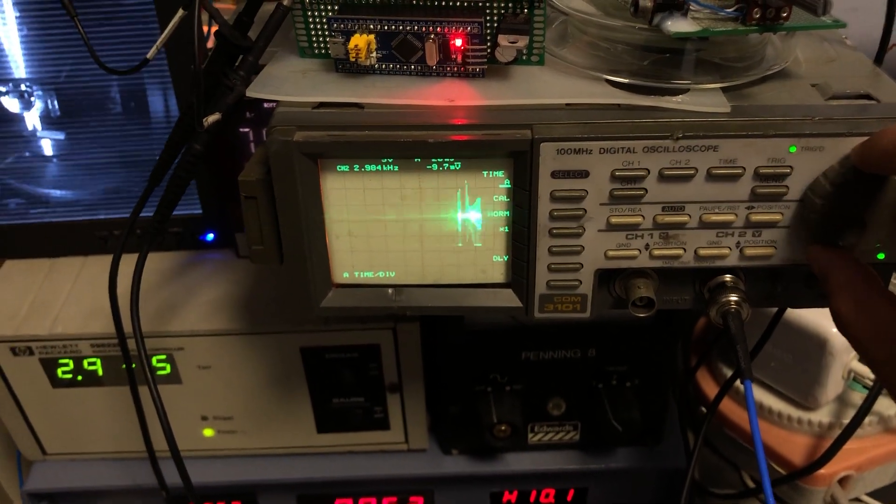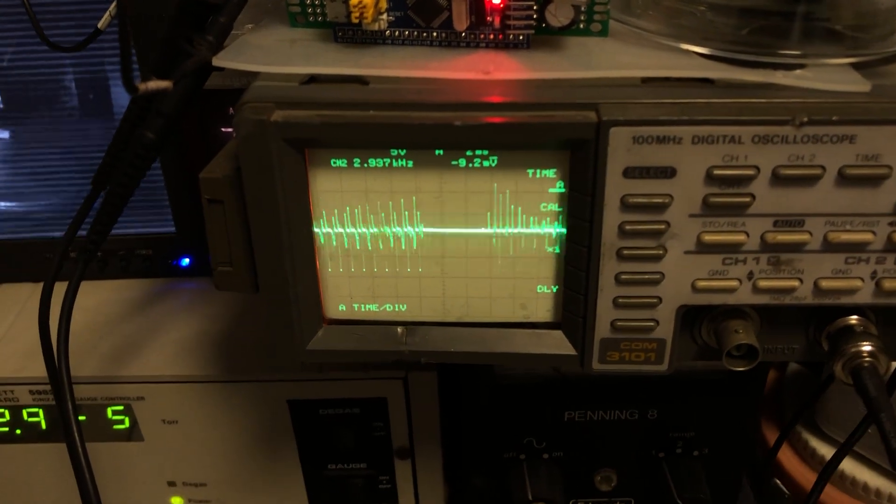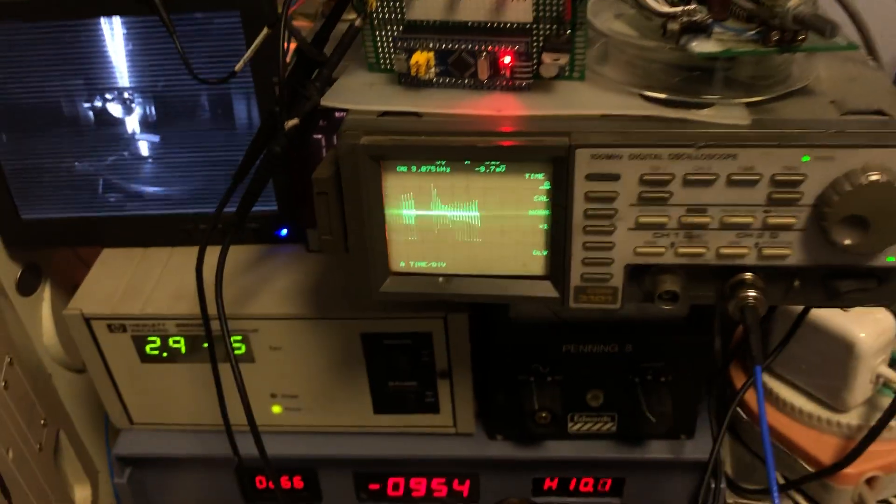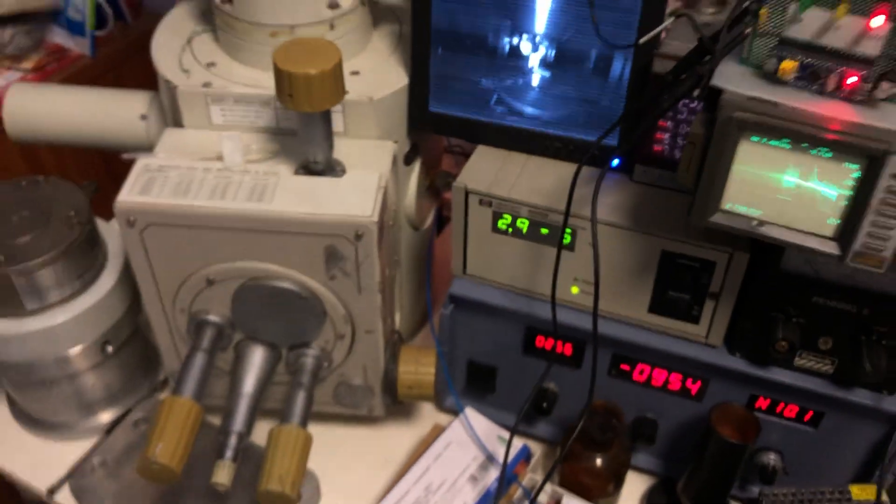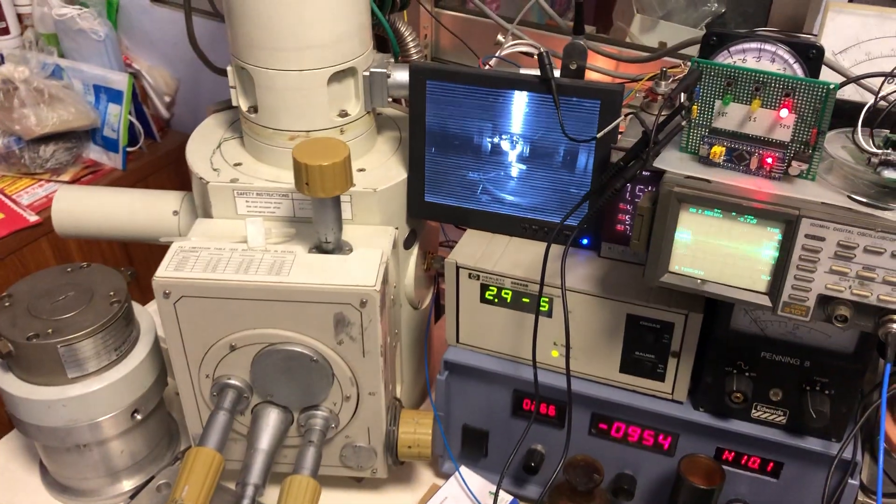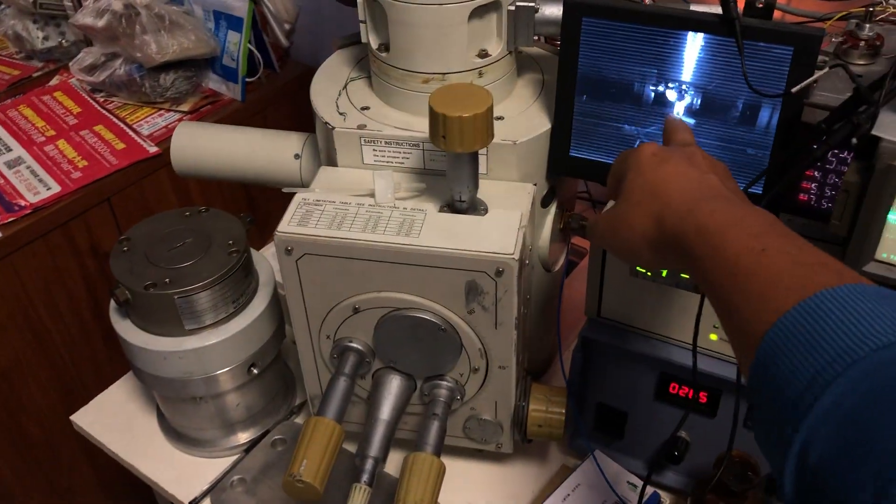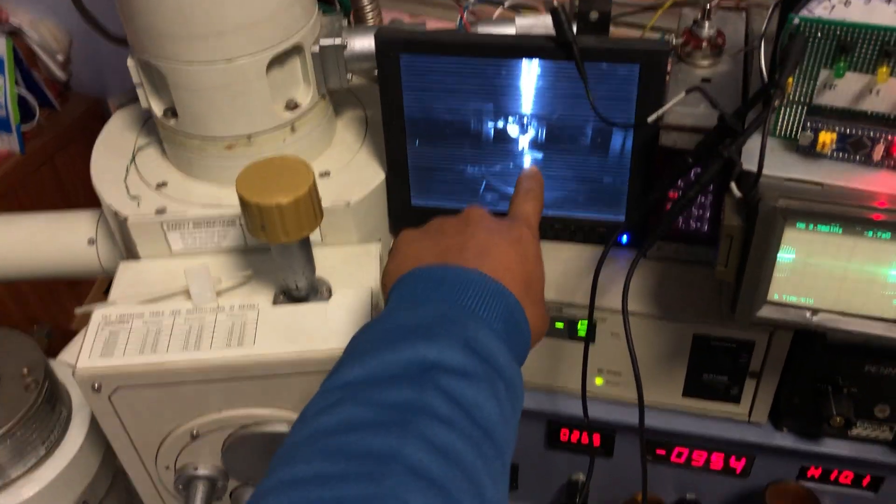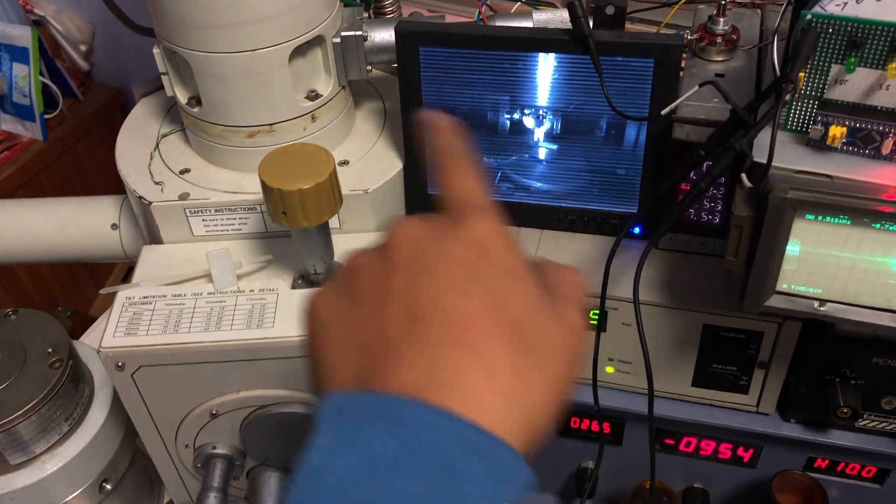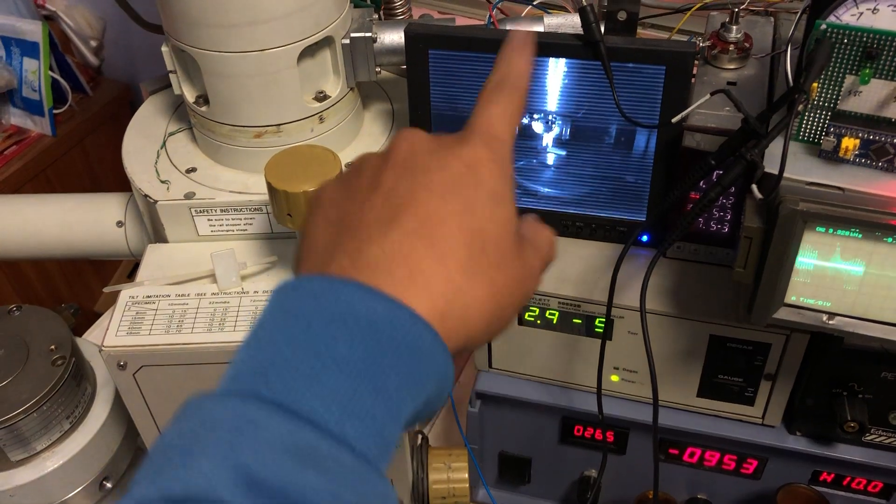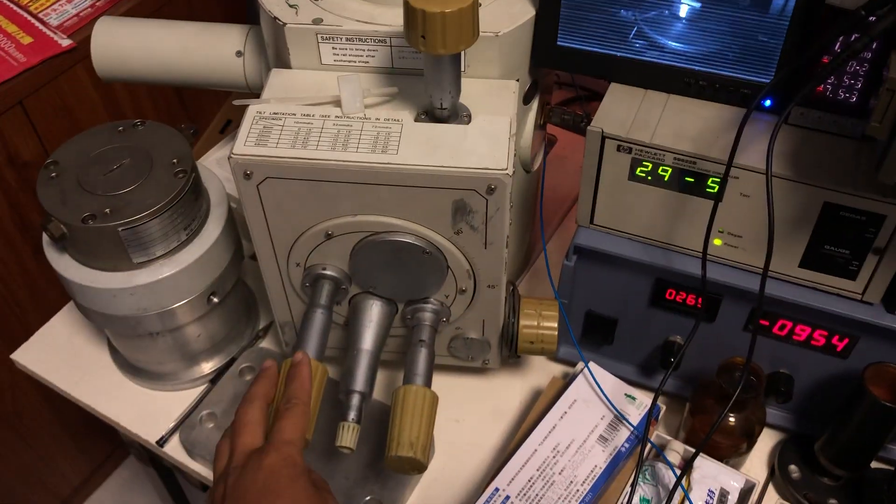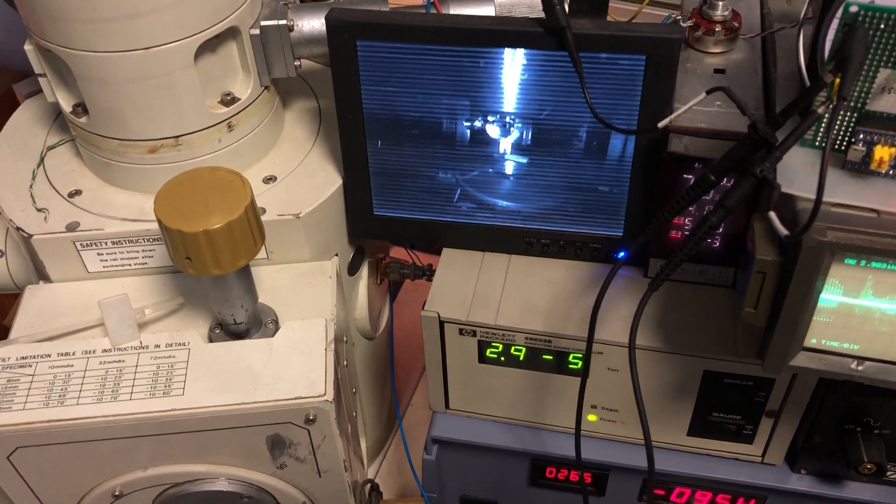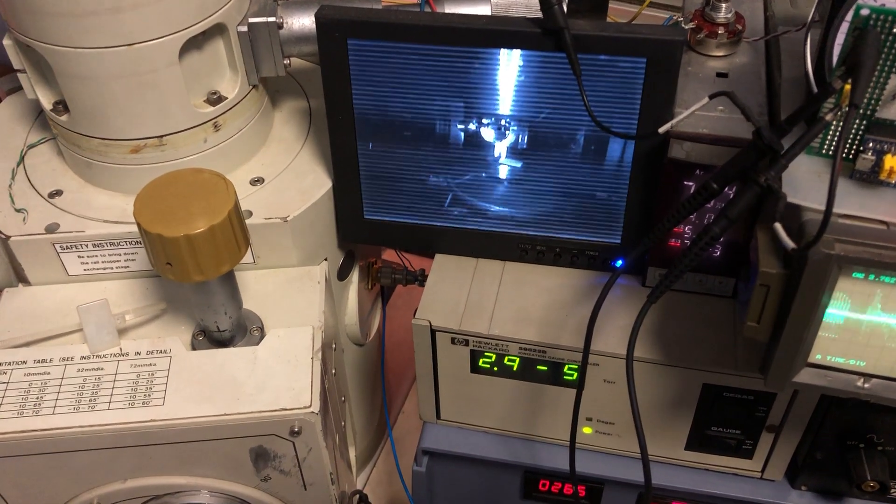Here you can see the video signal output from the microscope itself. So here you can see it on the monitor screen, the digital camera monitor screen. There's a phosphor disk on the sample holder. Now the electron beam is not scanning on the phosphor disk. Now if I move the X knob and turn it through, you can see it.